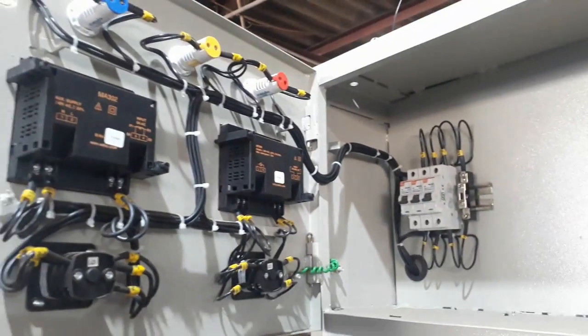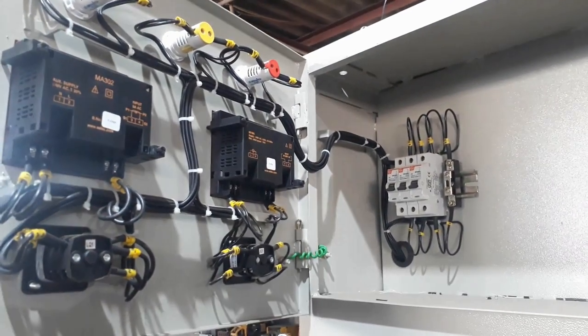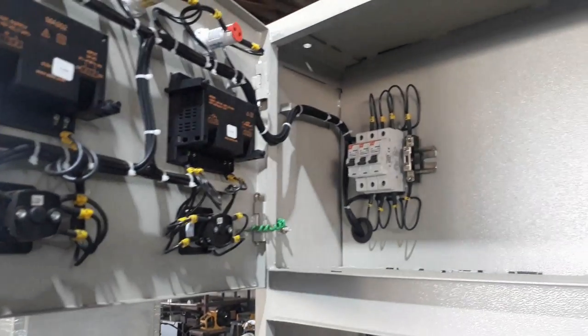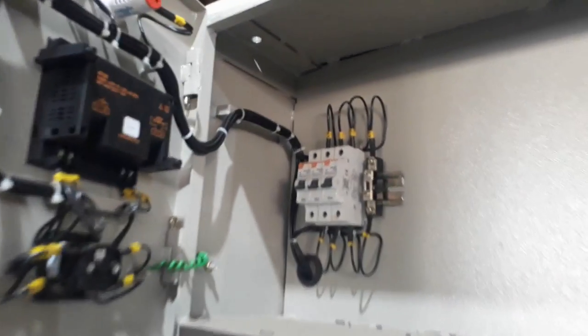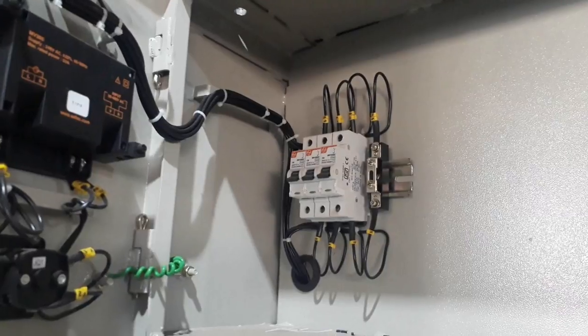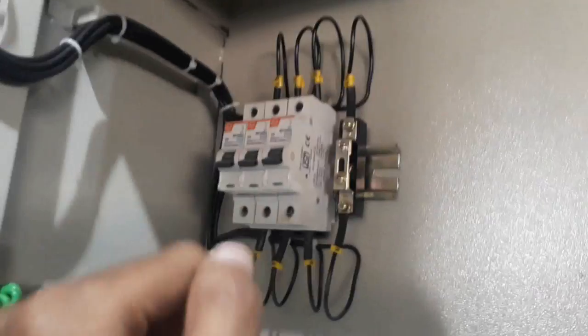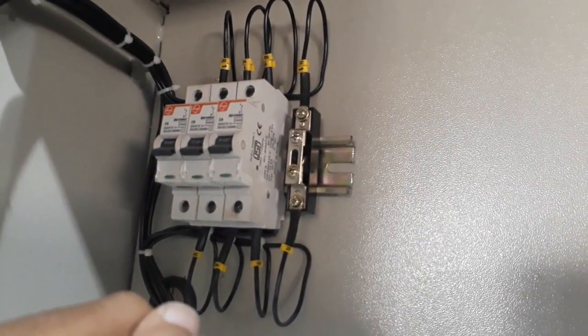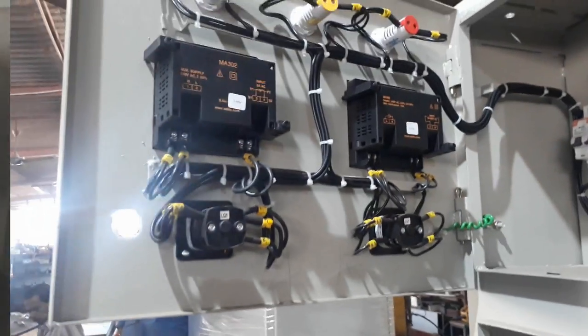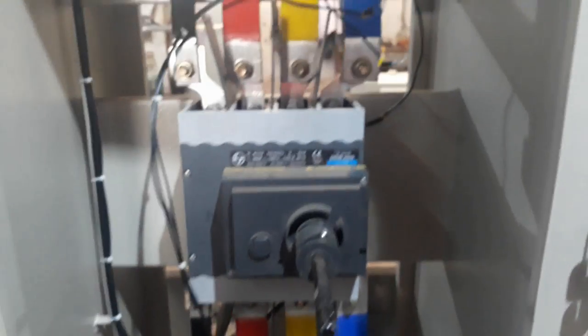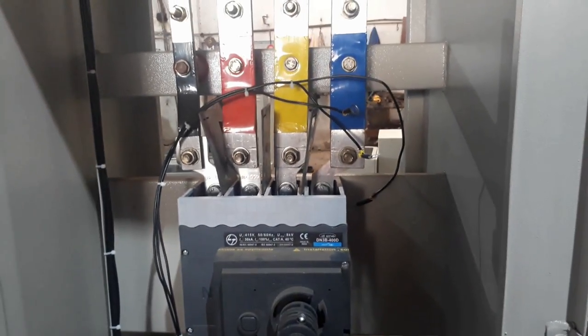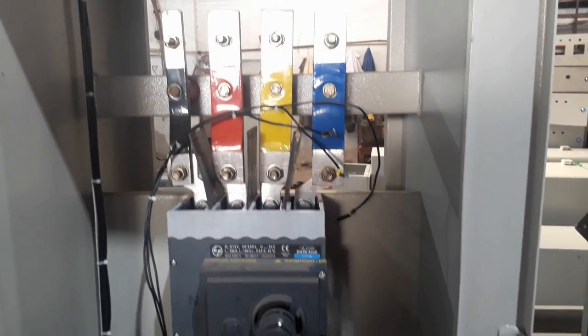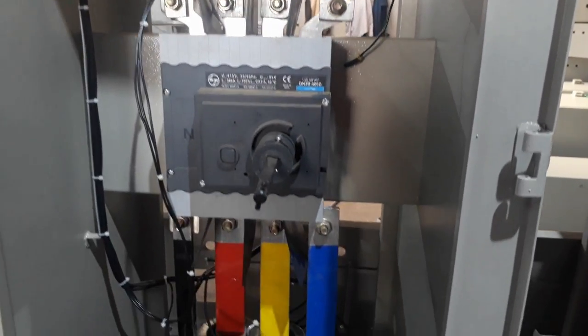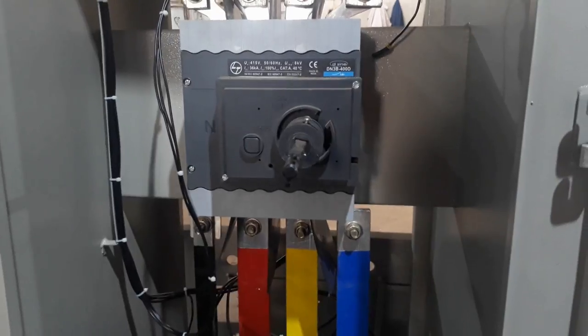The wiring of the voltmeter and ammeter I have shown you in the previous panel videos. You can check that video for the detailed wiring of the voltmeter and ammeter. This one is a circuit breaker, three circuit breakers for the protection of the three phase indicators. So this one is a main MCCB here. This one is a 400 ampere main MCCB, and the incoming of the transformer is connected to the phase in of the MCCB.